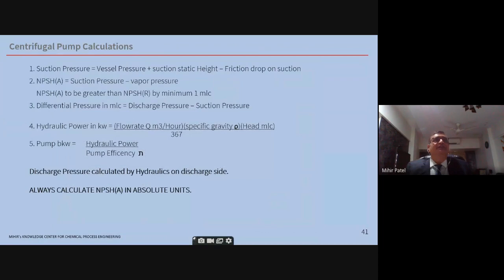Now, centrifugal pump calculations. The suction pressure is vessel pressure plus static suction height minus friction drop on the suction line. NPSHA is suction pressure minus the vapor pressure of the fluid at that fluid temperature and pressure. NPSHA is to be greater than NPSHR by a minimum of 1 MLC, 1 meter of liquid column. For a centrifugal pump, you always give differential pressure: the discharge pressure minus suction pressure. The hydraulic power formula is there, and the pump BKW is the brake kW, so you have to divide by the pump efficiency, eta. Always remember, NPSHA is to be calculated in absolute units.